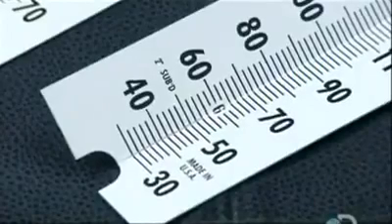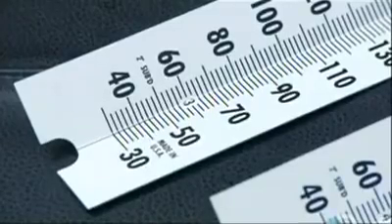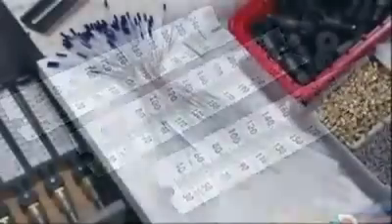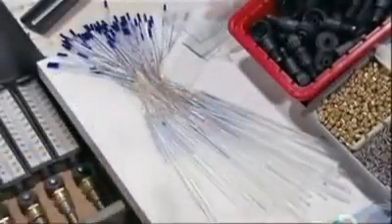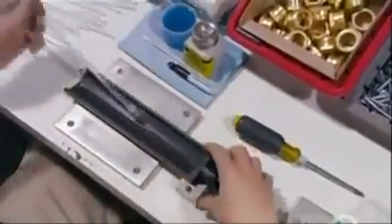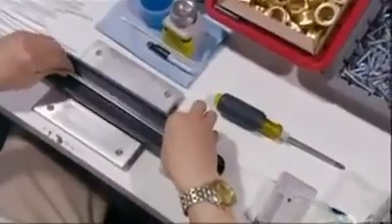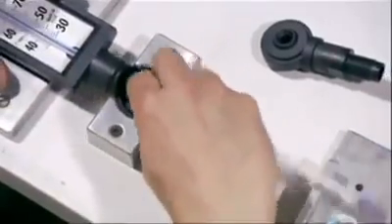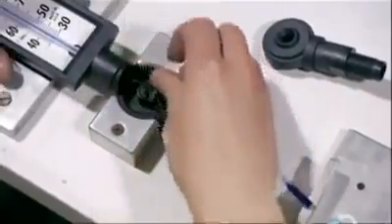They then match the thermometer with the corresponding scale. They install the top section of the thermometer in a case, which can be metal or plastic. They then choose the appropriate scale and slide it between the glass tubing and case. They wrap part of the wire capillary around a joint and then cap it.